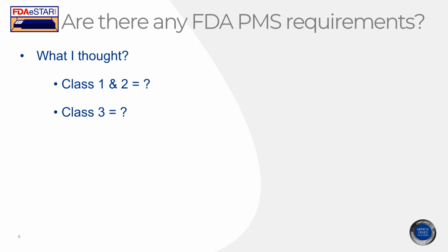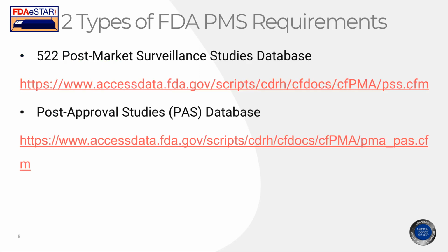Now, are there FDA post-market surveillance requirements? There's what I thought was the answer, and then when I investigated this for this presentation and another one that I did for a podcaster, I realized that everything that I thought was wrong. What I thought was there are absolutely no post-market surveillance requirements by the FDA for class 1 and class 2. And I thought that all class 3 devices required post-market surveillance all the time. And those were both wrong. So I'll get into what actually is required.